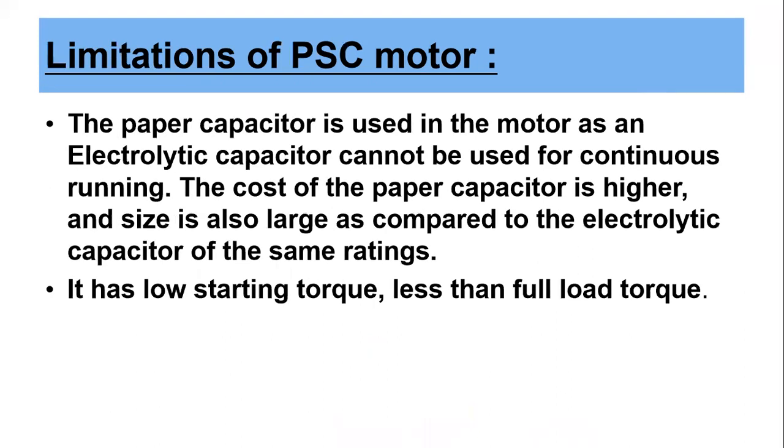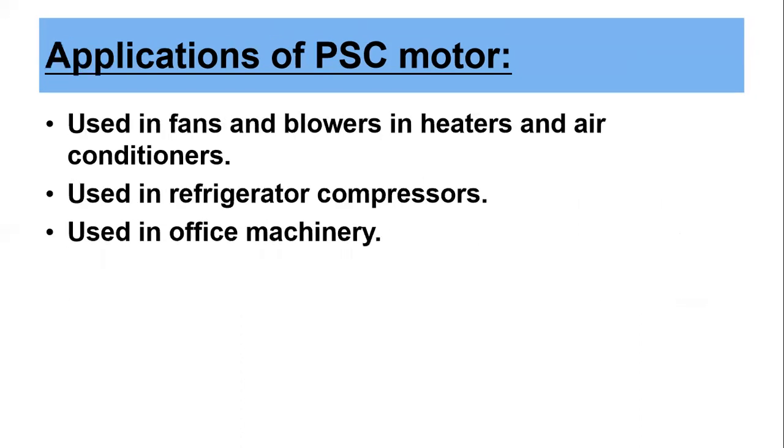And here are the limitations of the PSC motor: a paper capacitor is used in the motor as an electrolytic capacitor cannot be used for continuous running. The cost of a paper capacitor is higher and size is also large as compared to an electrolytic capacitor of the same ratings. It has low starting torque, less than full load torque.